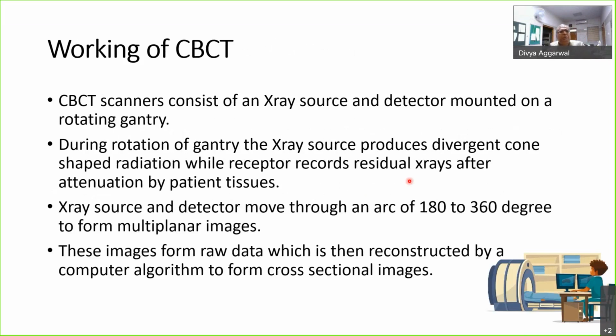What are the components of a CBCT, cone beam CT? It consists of an X-ray source and detector mounted on a rotating gantry. During rotation of the gantry, the X-ray source produces divergent cone-shaped radiation. Now, this is the most important thing: there is cone-shaped radiation, while the receptor records the residual X-rays after attenuation by the patient. That is true for the conventional CT also. I'll show the diagram in the next slide.